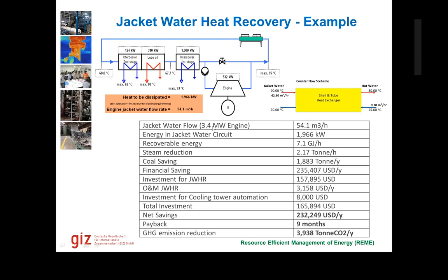So what we do is we use the flow rate of the jacket water. Then we see how much delta T we need on the jacket water side, and how much delta T we can gain on the demand side, using Q = m·Cp·ΔT and using the heat exchanger efficiency. So Q on the left hand side is equal to Q on the right hand side with the efficiency of the heat exchanger. So the recoverable heat on the right hand side might be a bit lower than the heat available on the left hand side, and this water flow rate on the demand side needs to be calculated based on the demand side flow rate. How much water do we actually need? If we need less water, then we'll have high temperature water. If we need a high water quantity, then we will gain less temperature in the hot water at the outlet. So using Q = m·Cp·ΔT, we can directly calculate the saving potential that is there.